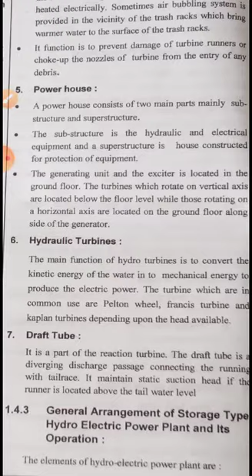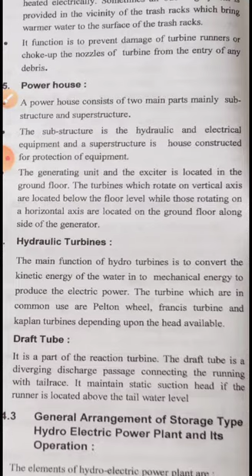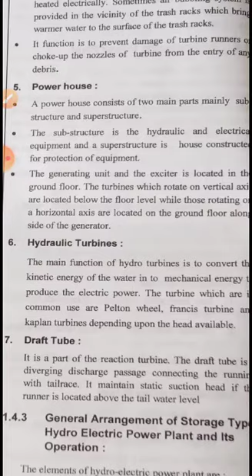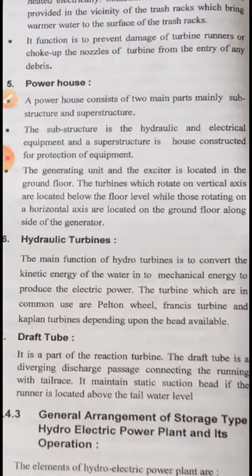A powerhouse consists of two main parts, mainly the substructure and the superstructure. The substructure holds the hydraulic and electric equipment, and the superstructure is the house constructed for protection of the equipment. The generating unit and the exciter are located on the ground floor. The turbines which rotate on a vertical axis are located below the floor level, while those rotating on a horizontal axis are located on the ground level floor alongside the generator.